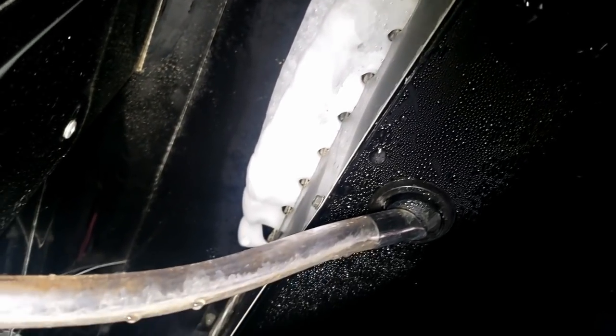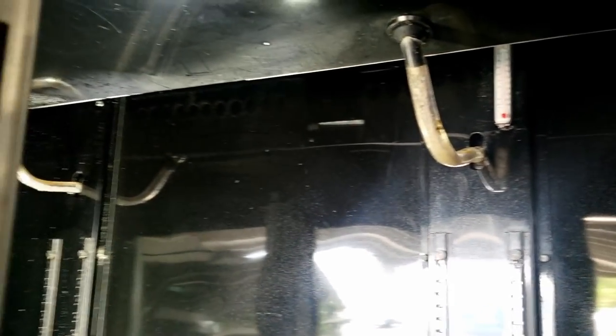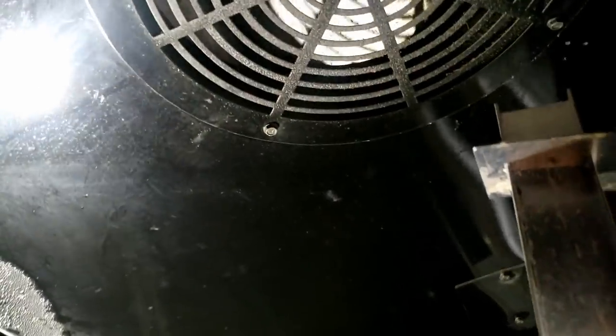Getting this thing taken apart. It's holding from the rear which is a pain. Looks like we've got two evaporators on this thing. Those drain lines have been growing stuff for a while — you can tell they haven't been cleaned in some time.